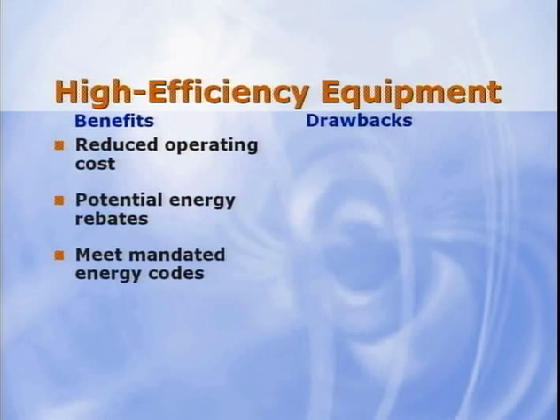Meeting state-mandated energy codes. Two states have adopted legislation requiring energy efficiencies based on the Consortium for Energy Efficiency's recommended level for packaged rooftop systems. The state of Maryland enacted legislation in January of this year requiring 10.0 EER on packaged rooftop units 20 to 80 tons, and California has adopted language in Title 20 requiring 10 EER for equipment 20 to 63.3 tons manufactured after October 1, 2006.